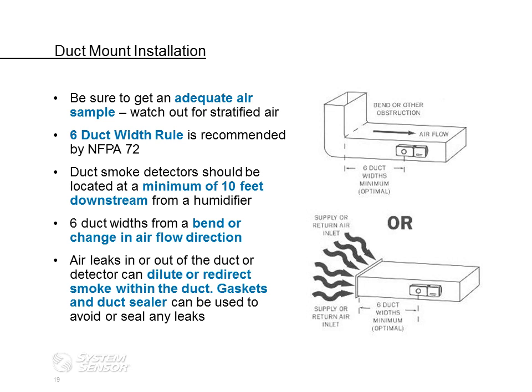The industry standard recommended is a 6 duct width rule. Now that is recommended by NFPA. That's not a required standard. It is a recommended best practice. The reason that it's not a true requirement is there are going to be some applications where you just physically cannot go that 6 duct width away. So if you're in that type of application where you can't get that specific spacing, then you basically have to do the best you can to try and avoid stratified air and make sure that you still have a proper air sample flowing across the head.